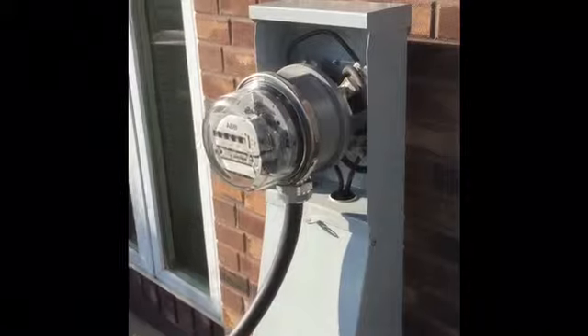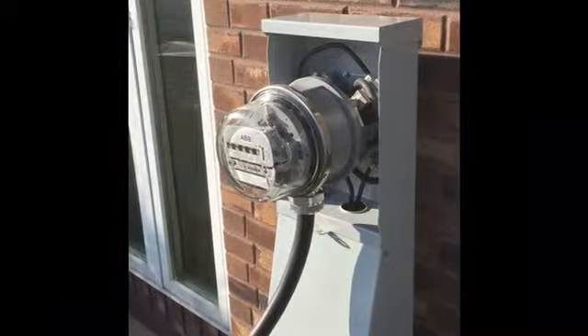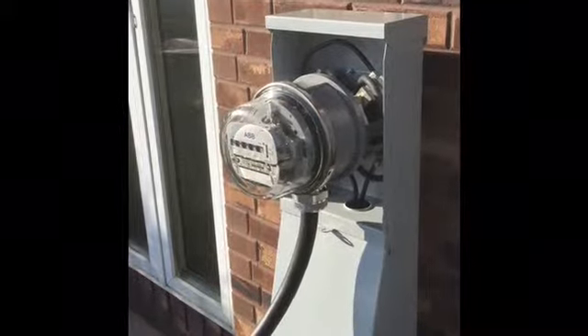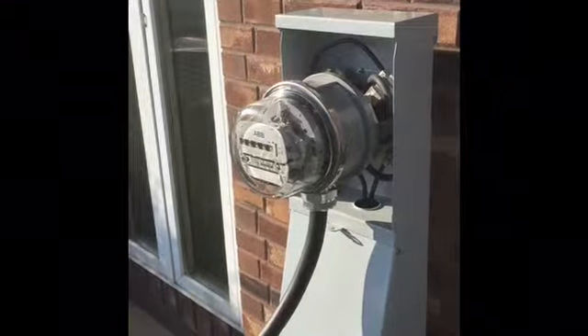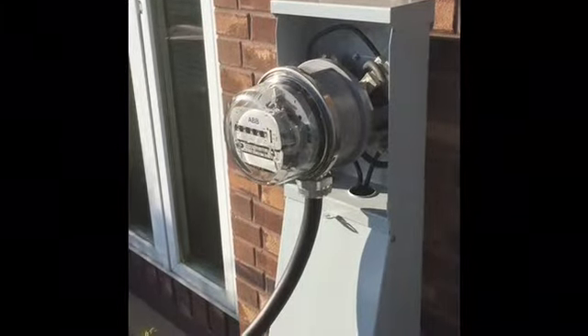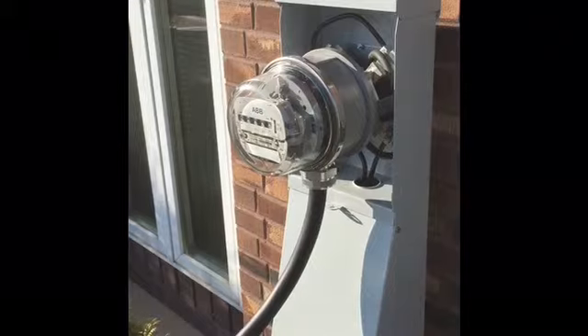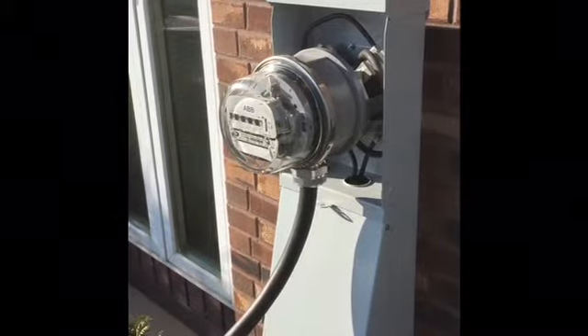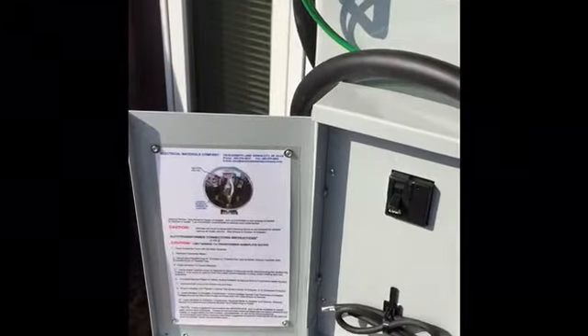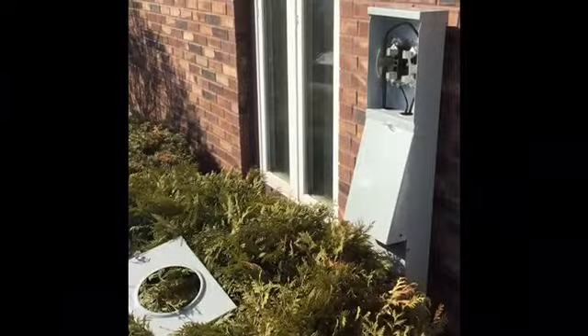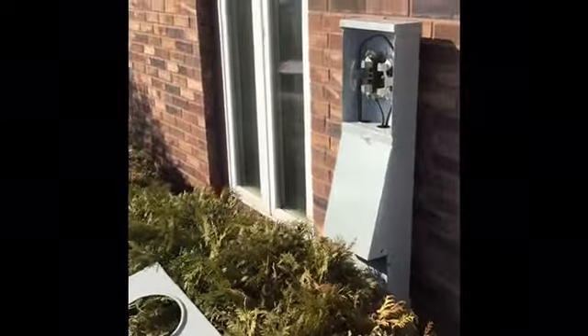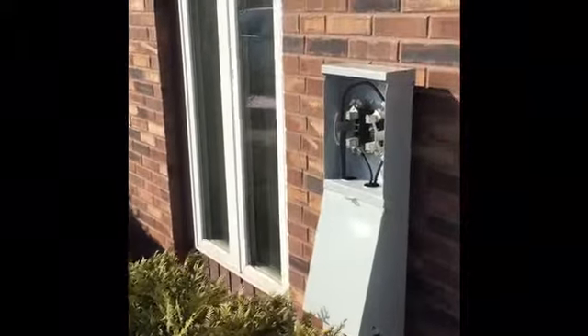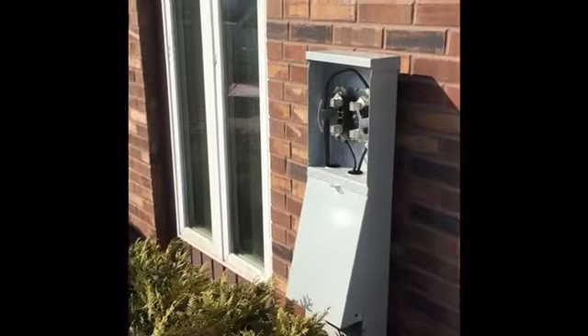Back to off. So after opening up the breaker, then we can go and disconnect all of the meter adapter and the meter and then neutral pigtail, and then we can go on to the step where we actually are going to install this on the meter sockets. Then what we want to do is restore the meter cover back on. We're going to put the meter cover back on the meter socket there, without the meter in it.